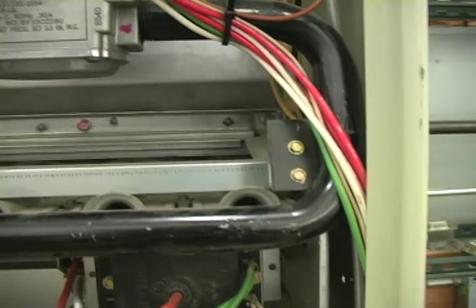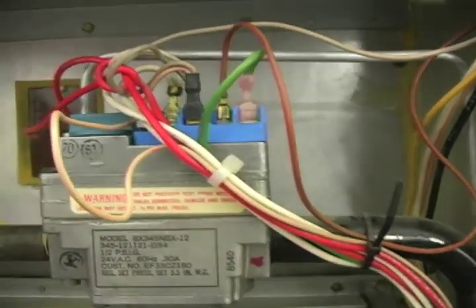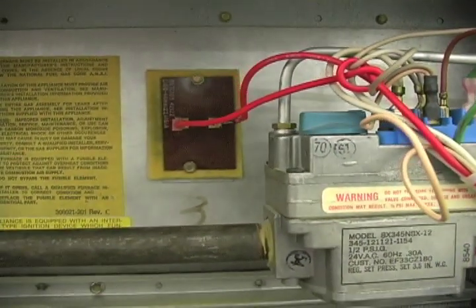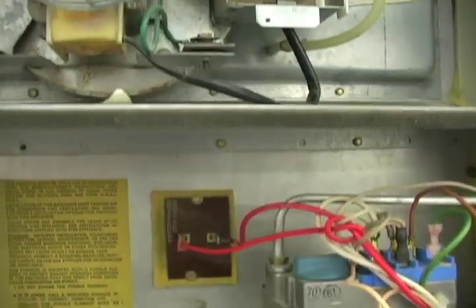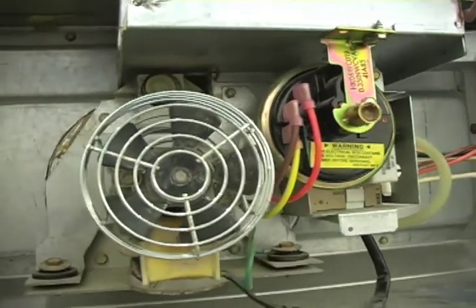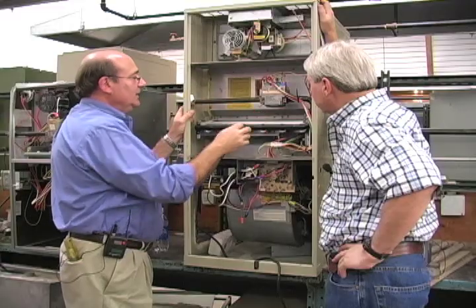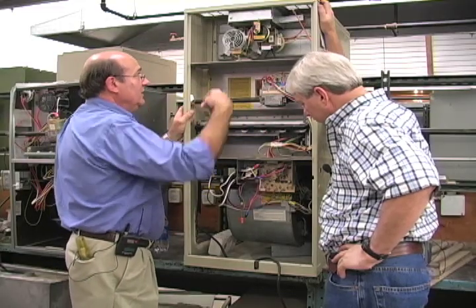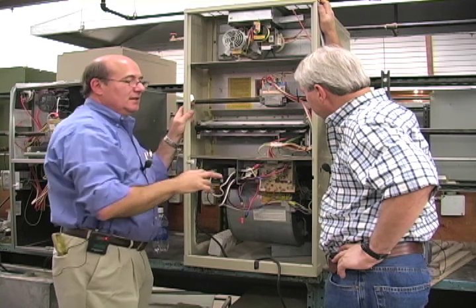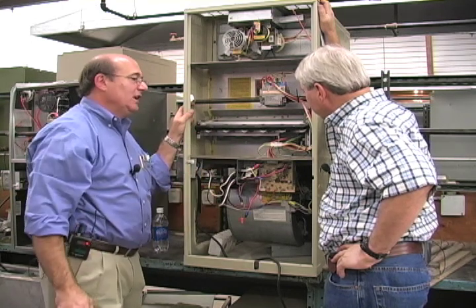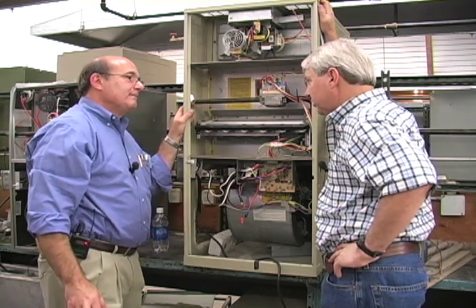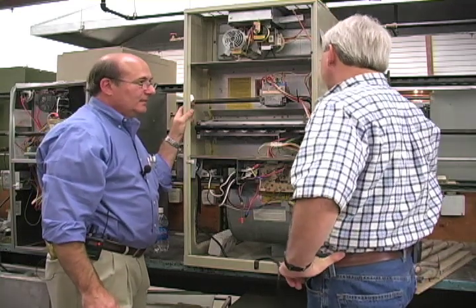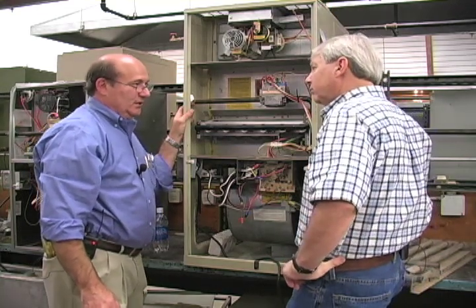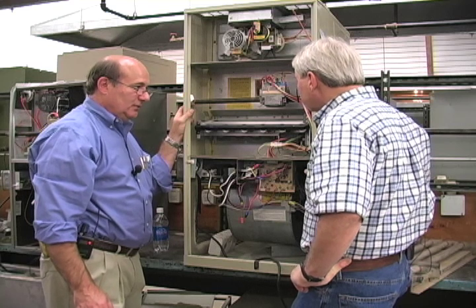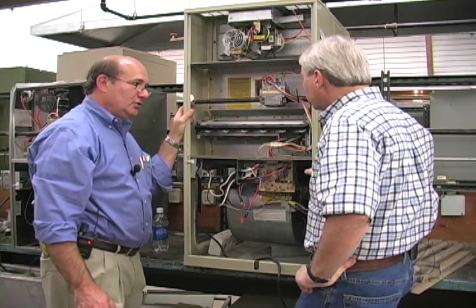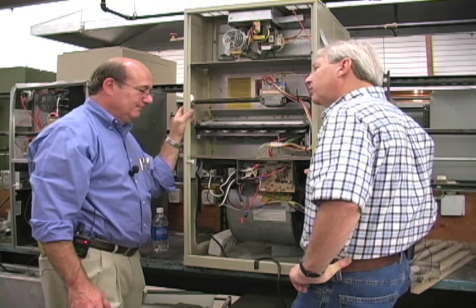And just as an aside, there are a handful of furnaces out there that are forced draft, where they have the combustion blower motor on a sealed heat exchanger that pressurizes the heat exchanger. And so air is being forced in instead of forced out and drawn in. That's just a slightly different variation on the theme. So that's a sealed burner chamber? That's correct. And that would be a forced draft combustion furnace rather than an induced draft. So it's pushing air through rather than pulling air through.